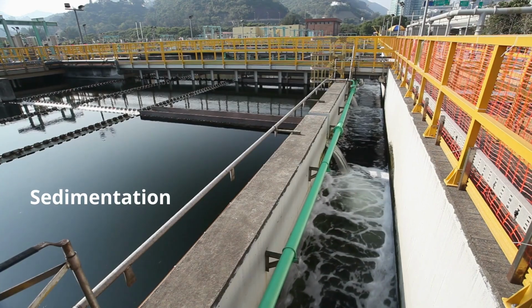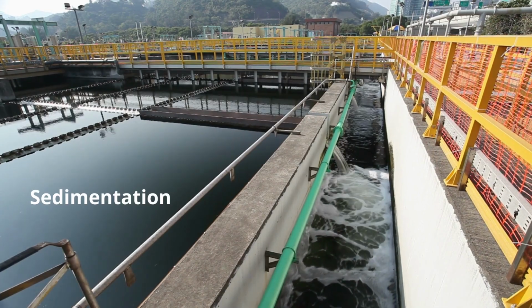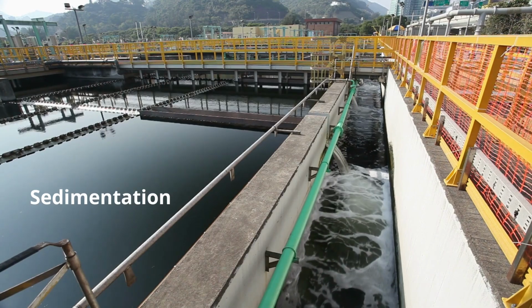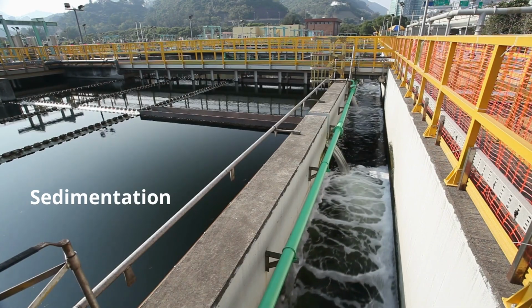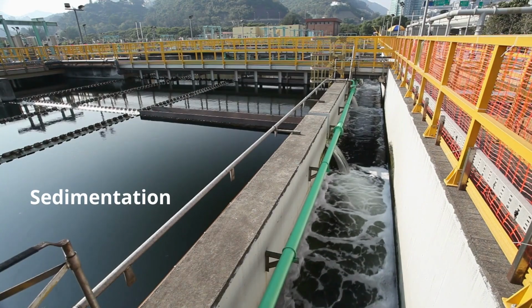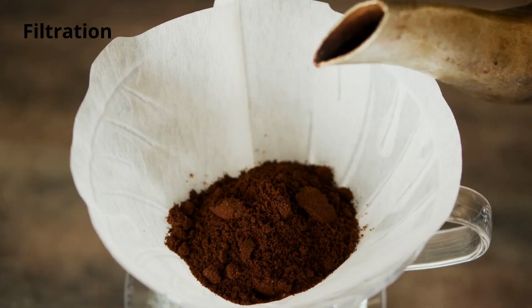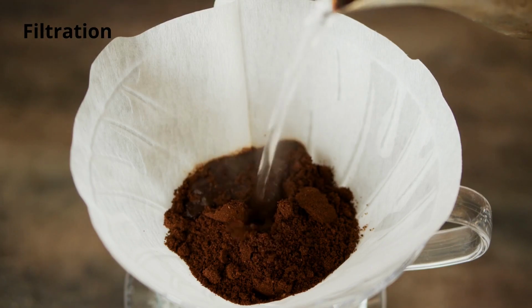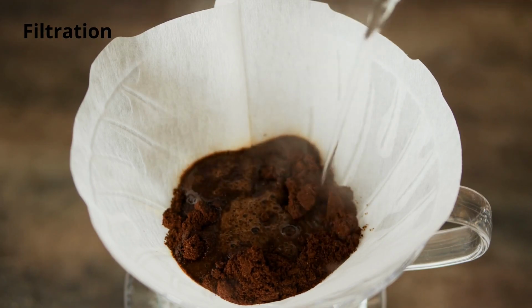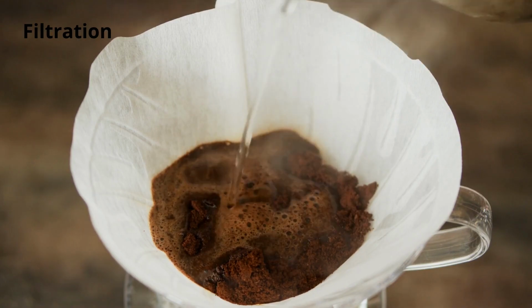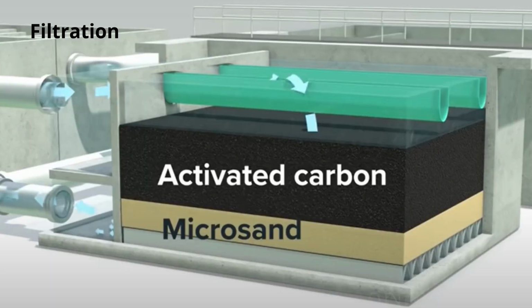The reason clarification occurs before filtration is so the majority of suspended material can be removed prior to filtration, which avoids overloading the filters and thus allows much more water to be filtered before the filters must be backwashed. Clarified water enters the filters from the top. Gravity pulls the water down through the filters, where it is collected in a drain system at the bottom of the unit. There are many different types of materials used in filters, the most common being sand and gravel.